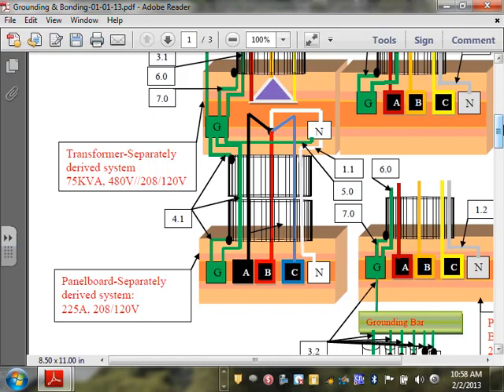You guys have seen these ones that stand like this. When you tighten them, they eat into the panel. Better connection. Or a grounding bushing with a jumper, or a wedge that you put behind the lock nut here, and you tighten it to eat into the pipe. So there's a bunch of options that you have here to bond that conduit. Any comments, guys? Any questions about bonding the conduit?